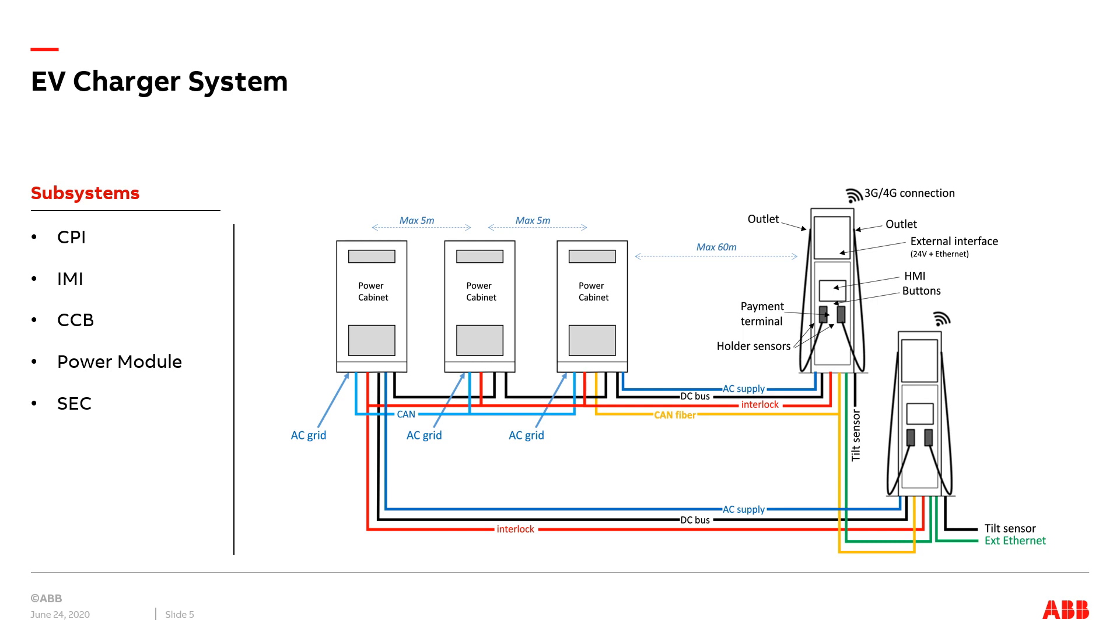The five main boards are CPI, IMI, CCB, Power Module, and SECC. CPI stands for Charging Protocol Interface which is a component responsible for EV connection detection and communication. The isolation monitor interrupter is controlled by CPI for circuitry protection.